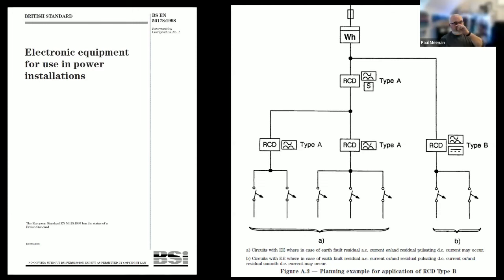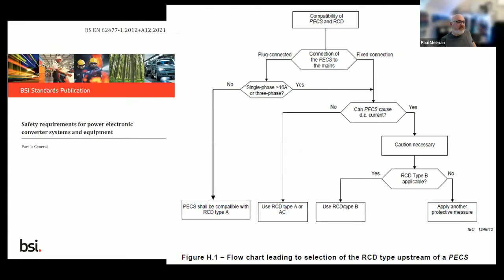So this is what I keep saying to people: configuration is key. Configuration of your protective devices, configuration of your earthing is incredibly important. If we fast forward to 2021, it's actually 2022 that came out, and it's mainly a product standard. Electricians generally don't know about it, but I find this chart quite fascinating. So BS EN 62477 part one talks about power electronic conversion systems and compatibility with the RCD.